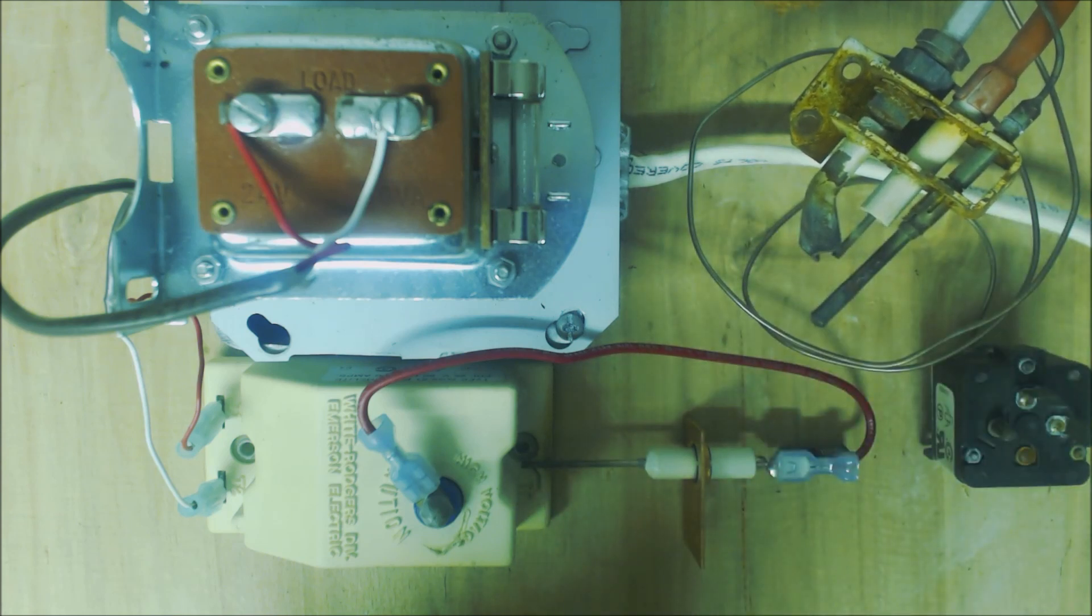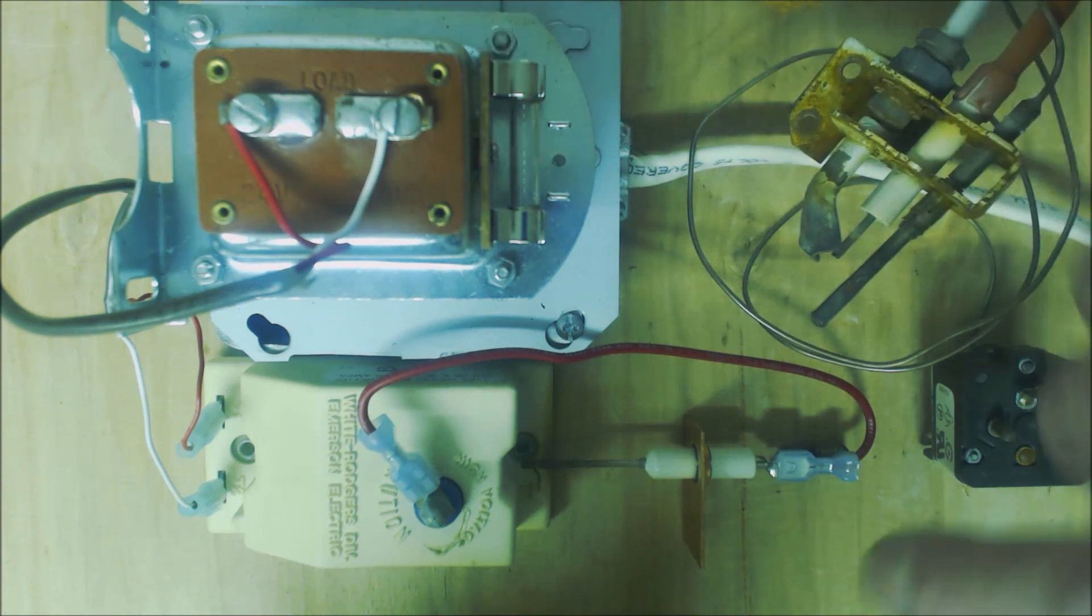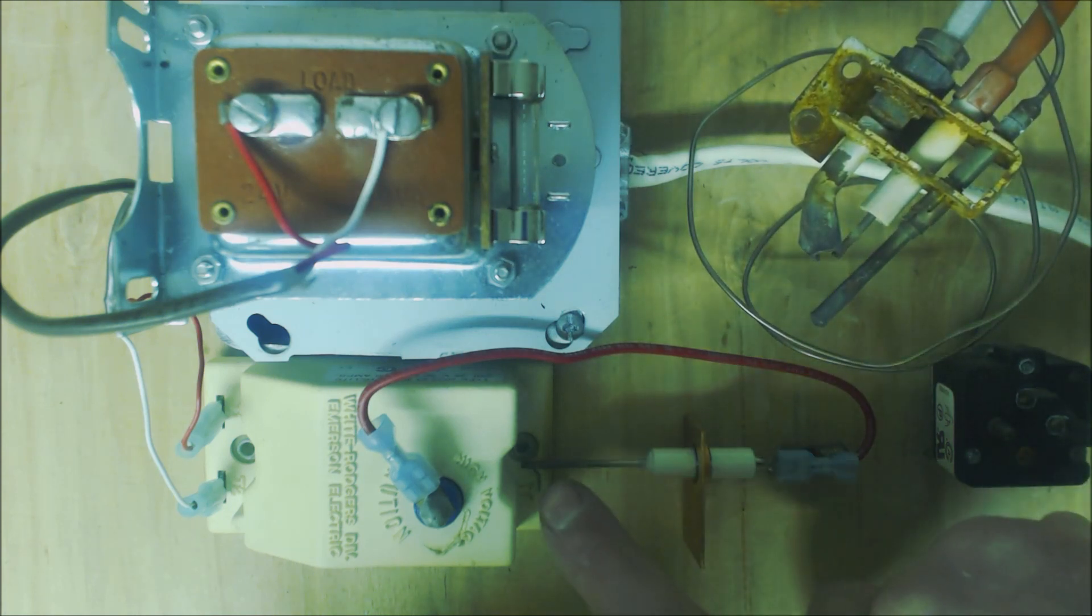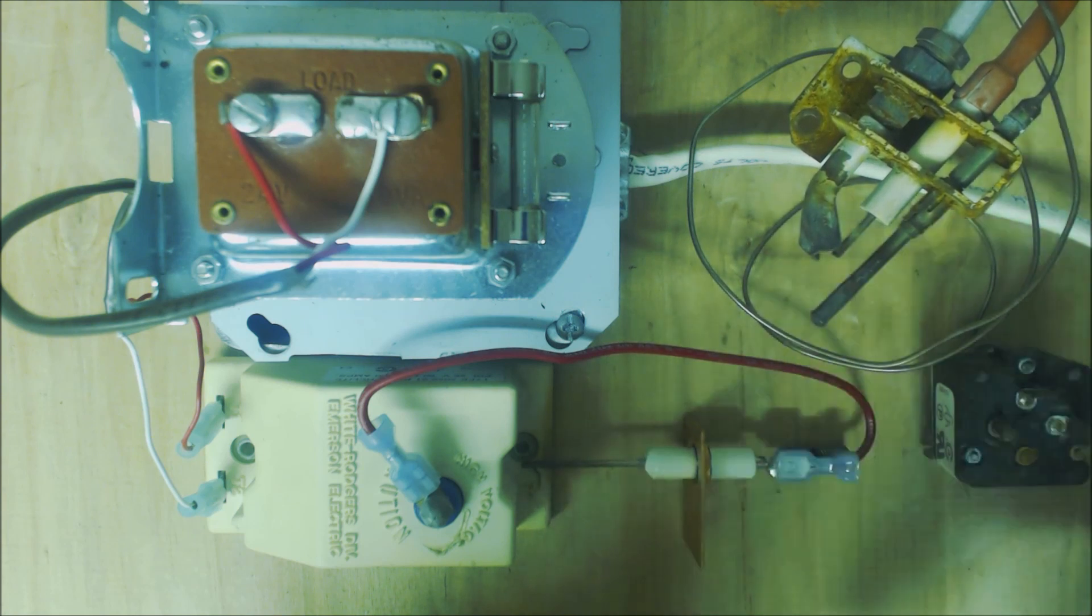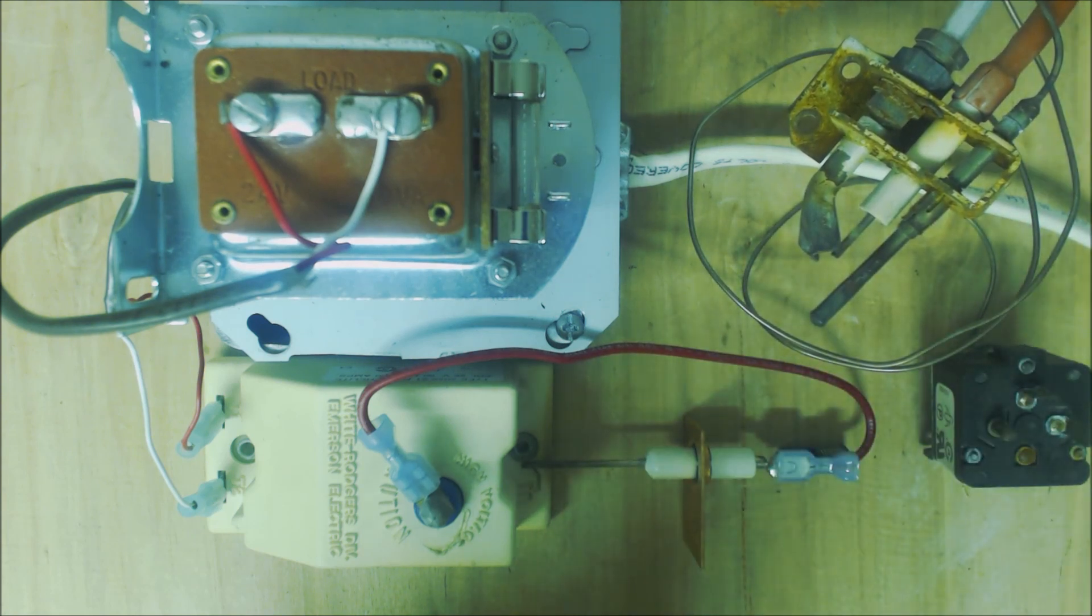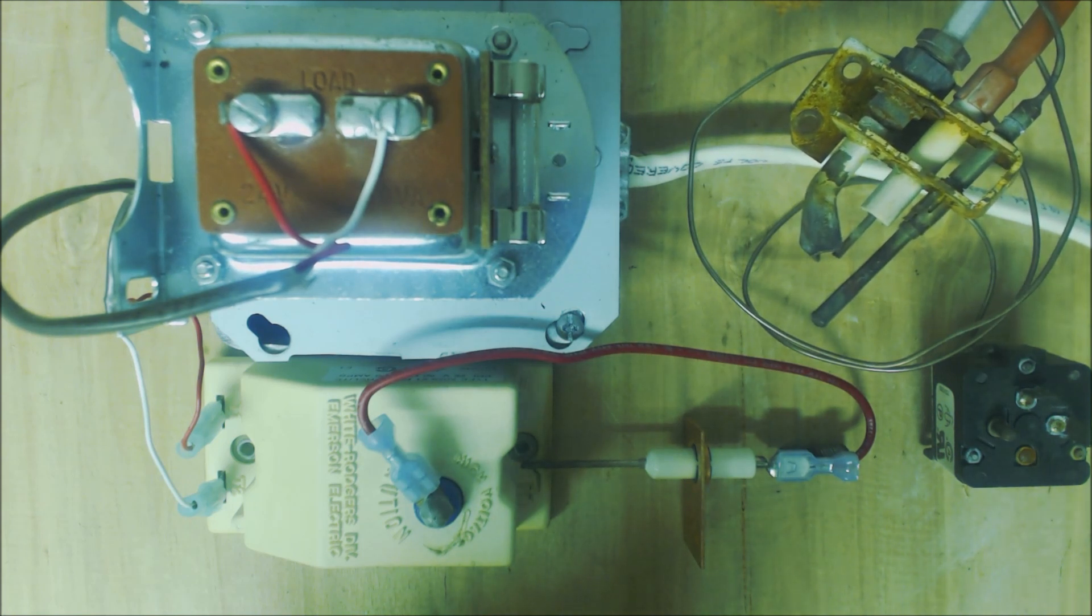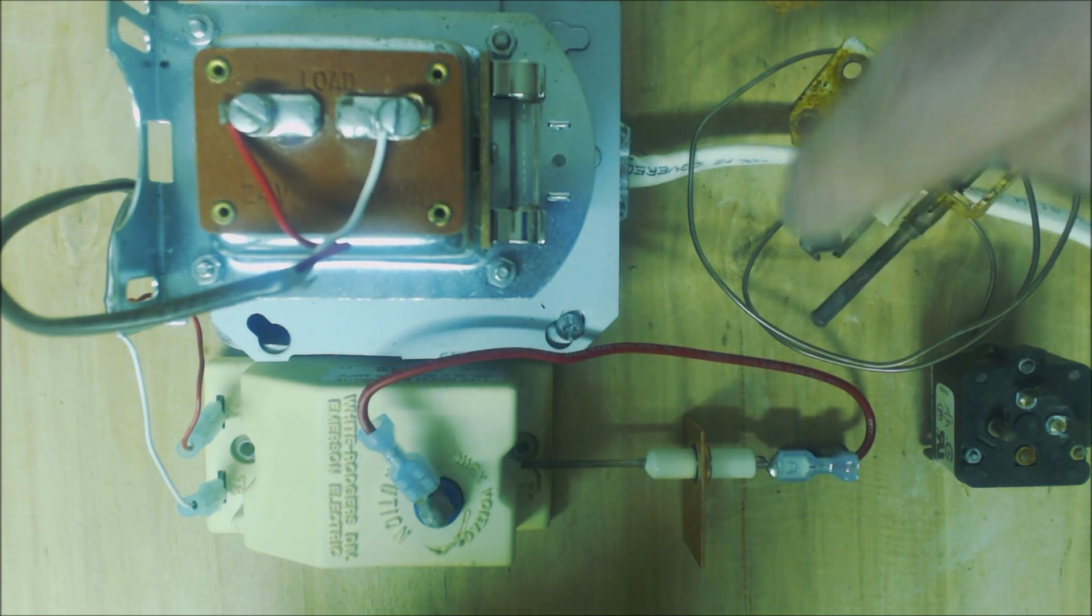I'm going to turn the voltage on - the 24 volts to the transformer - and we're going to have about a 6,000 volt spark right across here. It's going to do it intermittently. You see that spark right there - that's what's going to occur right at the pilot tube.